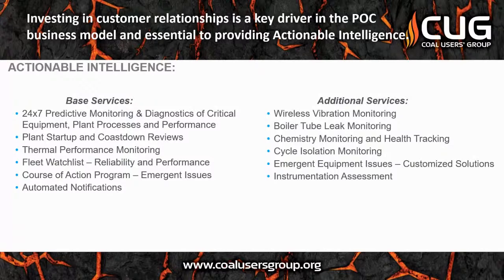Again, the POC, we're a 24/7 operation, so we can provide additional monitoring, or more importantly, additional analysis of issues or data when the plants are going through the normal day-to-day business of operating and maintaining the plants. The POC also provides review of all plant coast downs and all plant startups. We've identified wiped turbine bearings on plant coast downs and provided the plant with timely information that's reduced outage durations. We review unit heat rate information within 24 hours of any unit startup. We've also helped minimize heat rate losses that occur with normal unit startups, so examples of like valves leaking by, stuck open, airbound feed water heaters, those sorts of things.